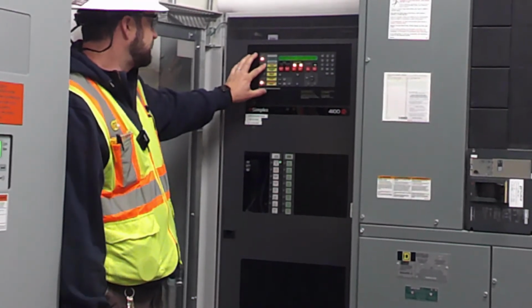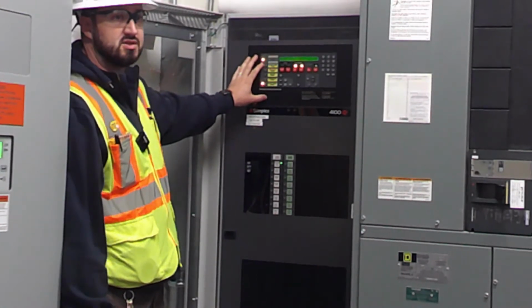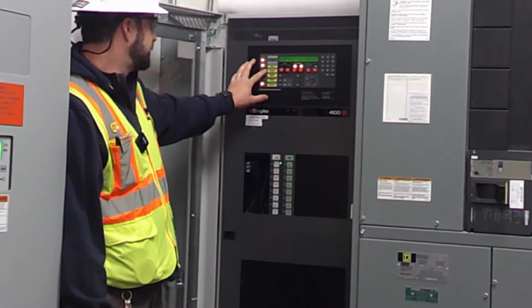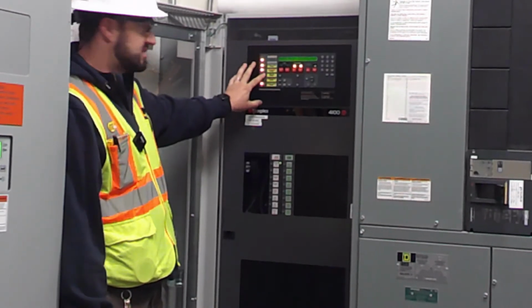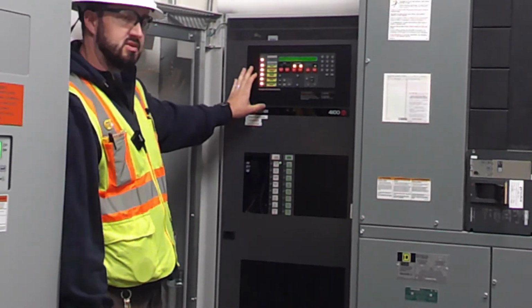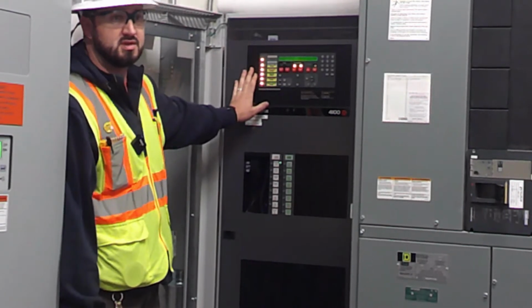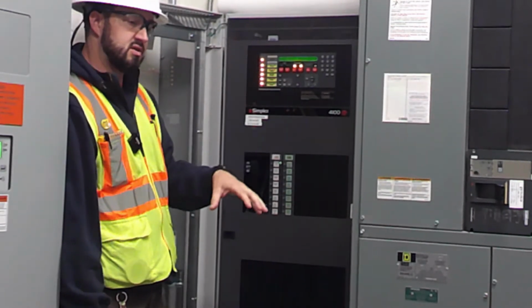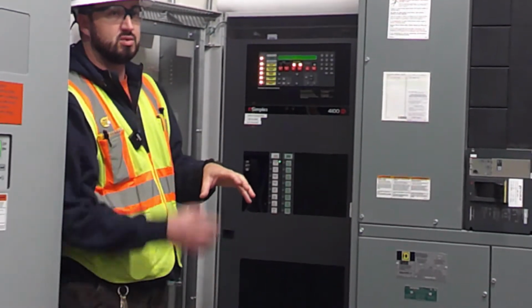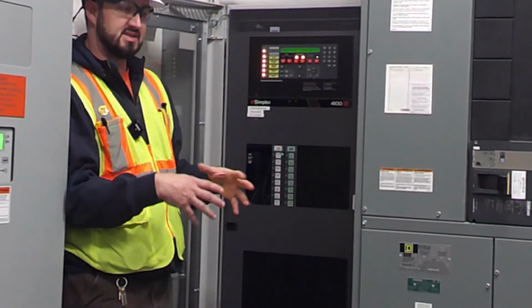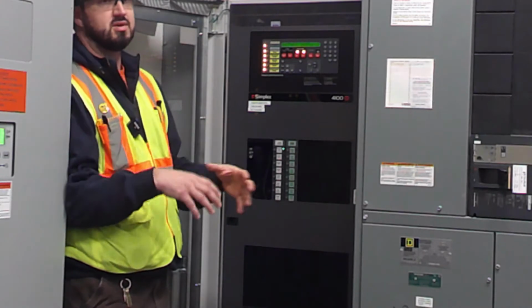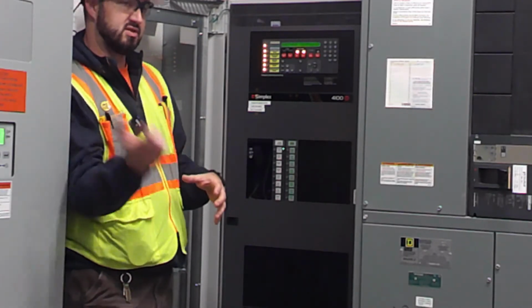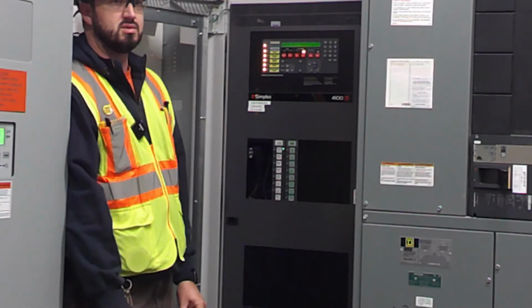These are all your speaker bypasses, so now no NACs or speakers will go off an alarm. Here's your door holder bypass, all your HVAC, fire smoke damper bypass. All buildings? That's all buildings. Everything in this building is programmed as a global. So if you have an alarm in this building, it will trigger every building. It's not isolated. Same with smoke dampers. If you have a smoke damper trip in this building, every smoke damper on the entire site will trip.